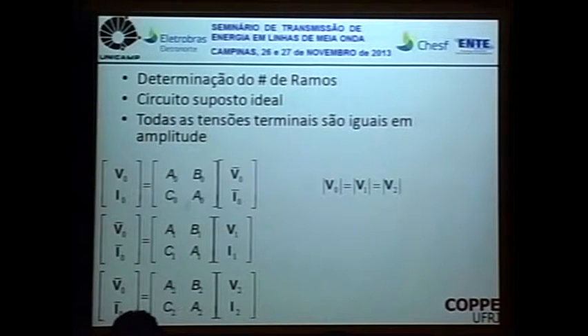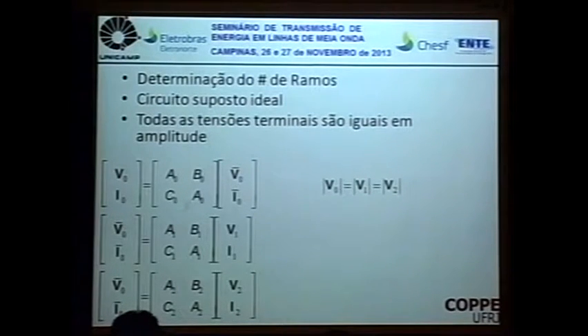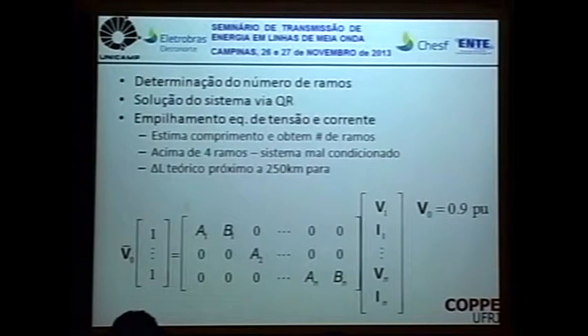The determination of the number of branches, for this we conducted this arrangement. We did something similar to the load flow of distribution when you have large radial systems, where I have the relation between the connection point and the several drainage points, as long as my connection point is single. This brings me to a system that is basically of this sort, where the voltage in my connection point of the input is single, and I can vary the voltages on the several load points. This system is a rectangular system. It is easily solved by QR.